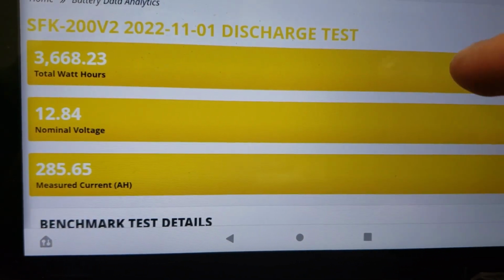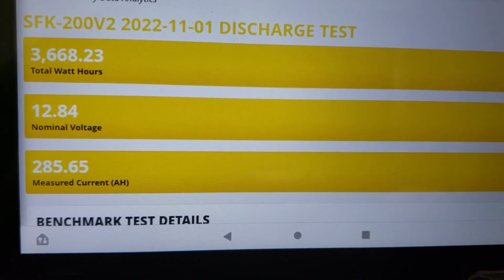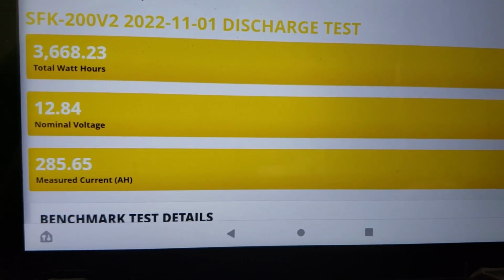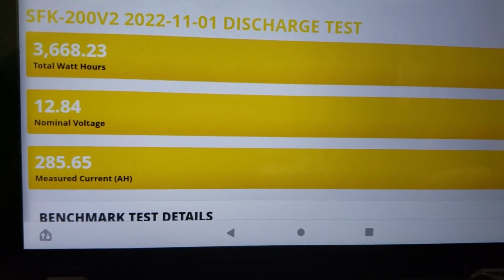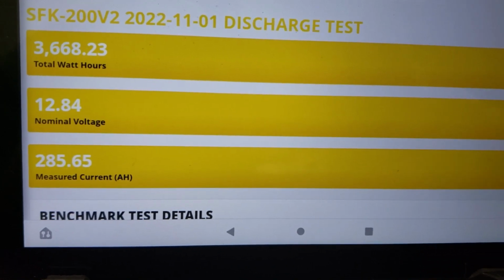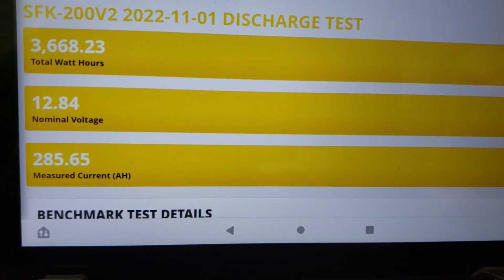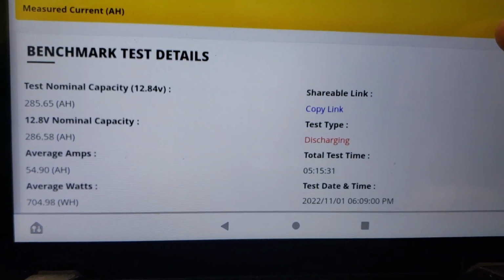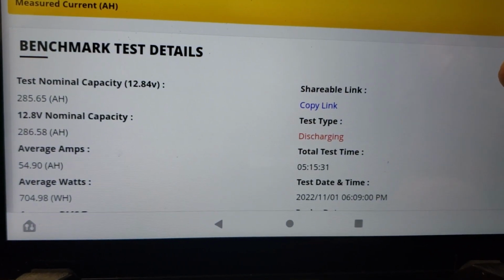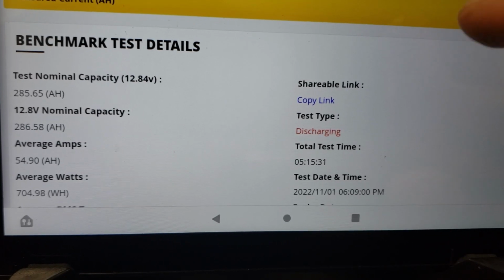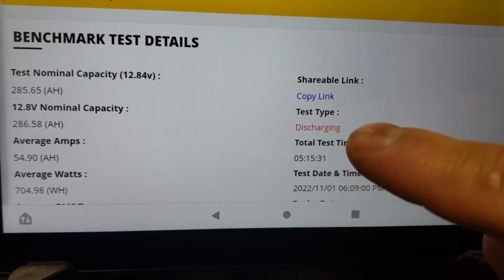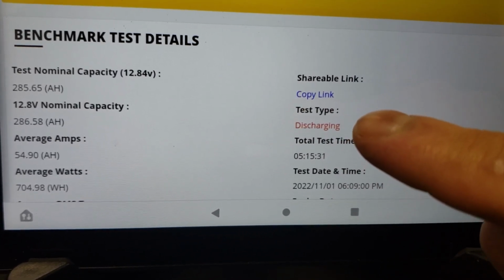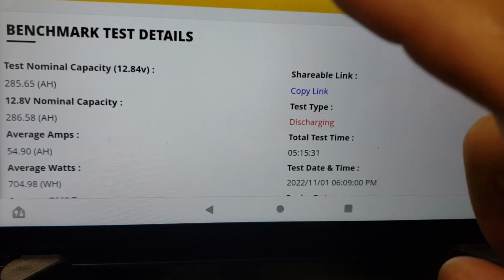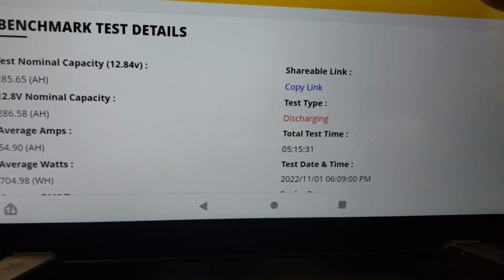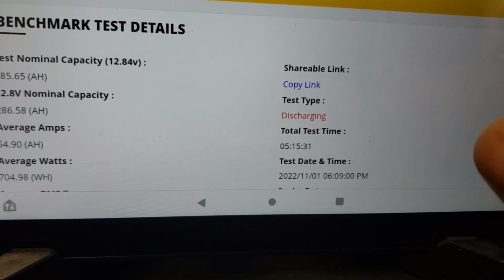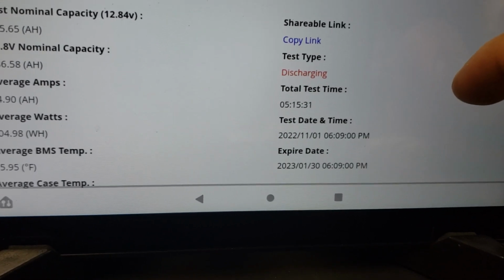It measured 12.84 nominal voltage. 12.8 is what lithium iron phosphate batteries are measured at. So it's actually testing higher than a normal nominal voltage. We can see that we tested to 285.65 at 12.8. But that is the equivalent of 286.58 if measured at the traditional nominal capacity of a battery.